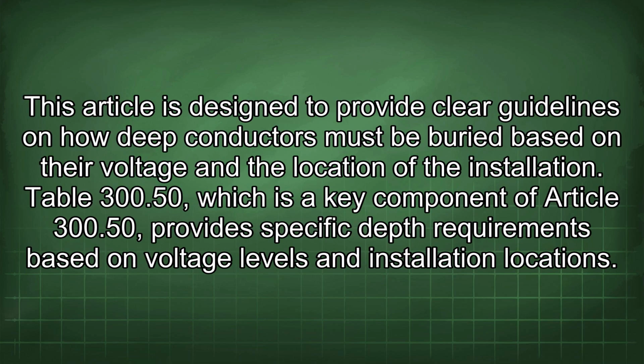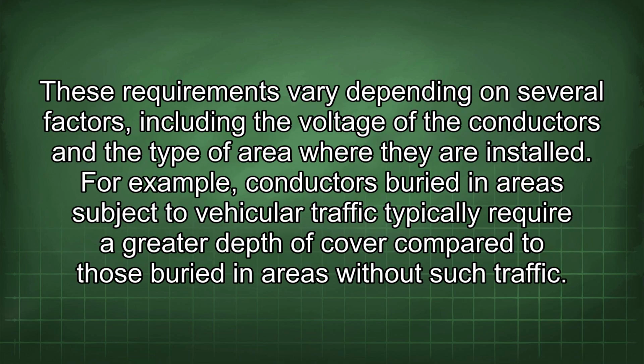This article is designed to provide clear guidelines on how deep conductors must be buried based on their voltage and the location of the installation. Table 300.50, which is a key component of Article 300.50, provides specific depth requirements based on voltage levels and installation locations. These requirements vary depending on several factors, including the voltage of the conductors and the type of area where they are installed.